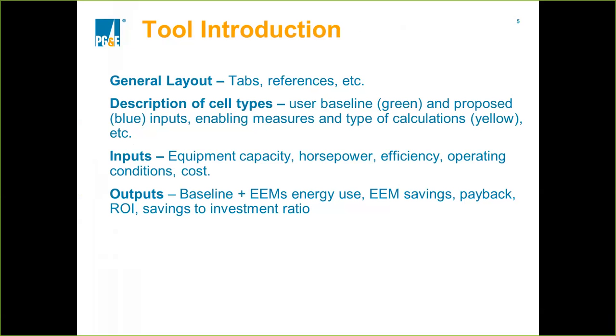There are different cell types: the green cell type means it's a baseline operating condition cell; if it's blue, it's a proposed input; and if it's yellow, it can mean two different things — either you are enabling a measure to see how much energy savings it can provide, or you are choosing the type of calculation. There are two types of calculations: 'detail,' which requires more information from the engineer, and 'simplified,' which requires simpler inputs for smaller projects or when you don't have a lot of information and just want to get a sense of the potential savings for certain measures.